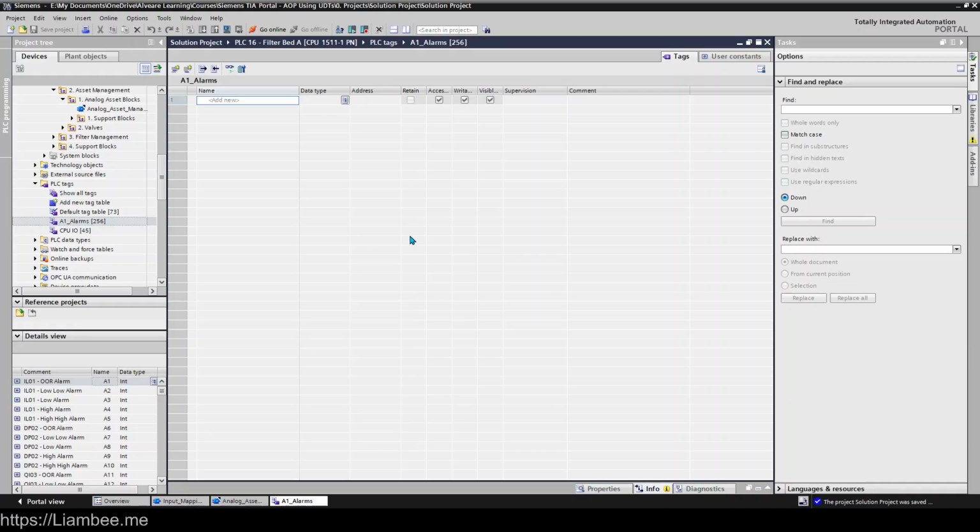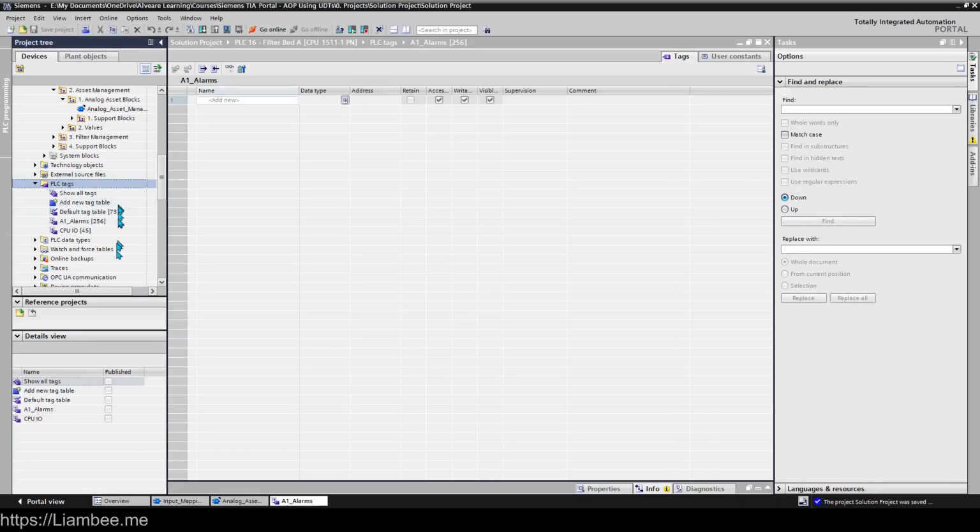It makes things really simple and easy, and you have a central alarm management system in the form of a standard block that can be used inside any asset. It can be used outside of any asset in any control system, sequence, and things like that. And it all hinges around a constant. So just like we can have constants in interfaces, we can also have constants in our PLC tags.